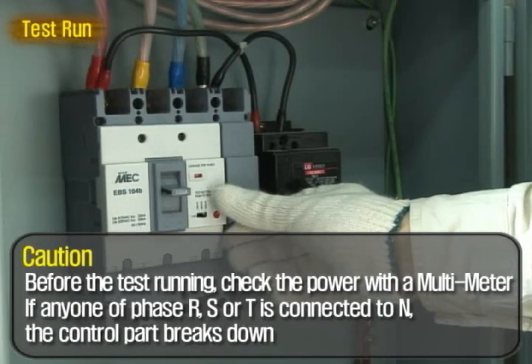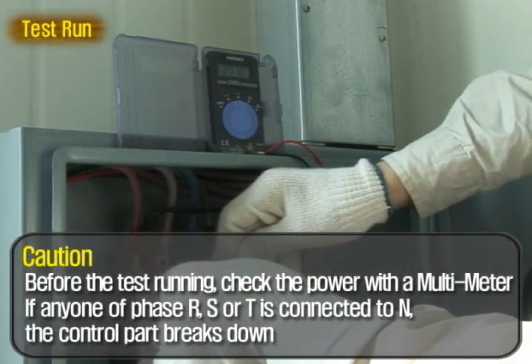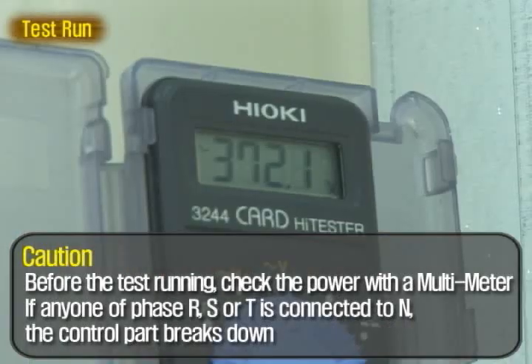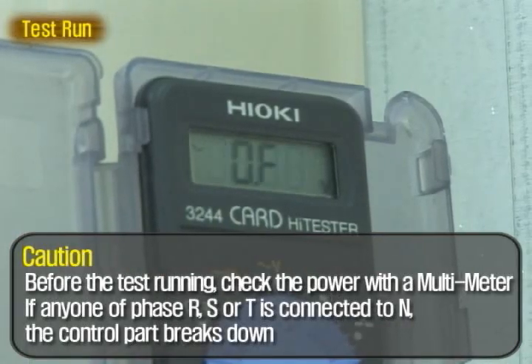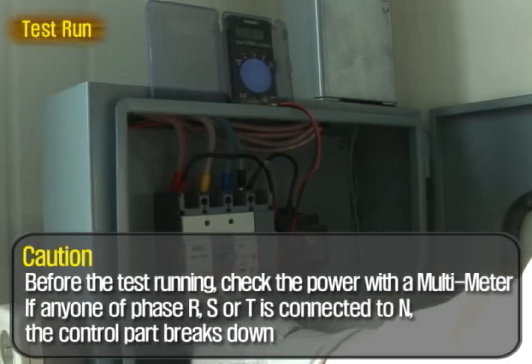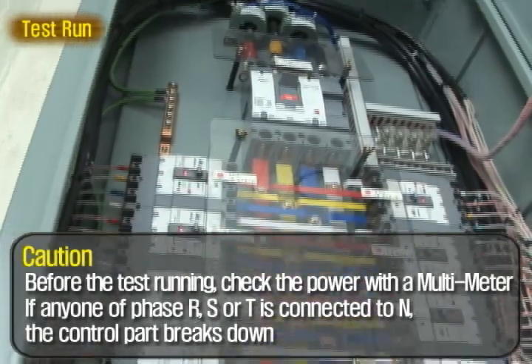Before the test running, check the power connections with a multimeter. If any one of phase R, S, or T is connected wrong to phase N line, the control part breaks down.